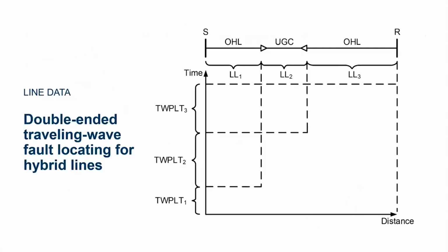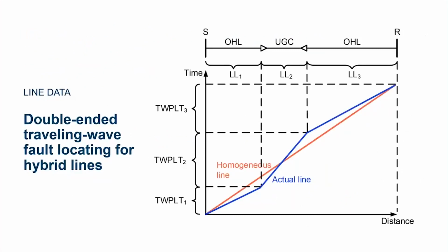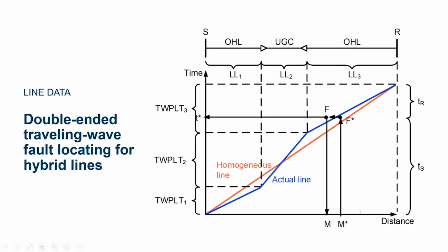How we determine if the fault is on the underground section is we tell the relay some traveling wave line propagation times for each section, and we give it an impedance for each section. The actual line is going to look something like this when we compare our distance to our traveling wave line propagation times. But what we do is we just draw a straight line. We draw a homogeneous line between the beginning and end of this hybrid line. Then when we have a fault, we calculate it on our homogeneous line, and then we project it to our hybrid line.